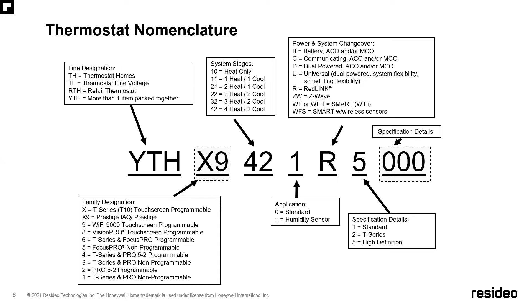The following two numbers in that example are 4-2, so that's 4 heat, 2 cool, telling you the cooling options very quickly. After that, the digit displayed is for an onboard humidity sensor, either a 0 or a 1. The next character is either an R for RedLink, WF or ZW for Z-Wave, and so on, as well as a U or D for the non-connected ones. So it's pretty easy to distinguish what thermostat you're looking at by part number, which helps with ease of ordering too.